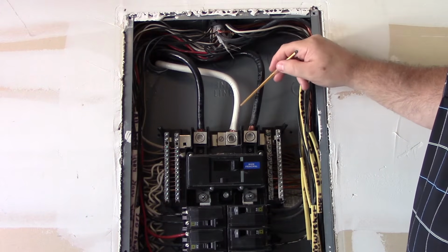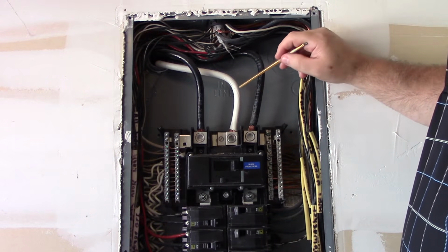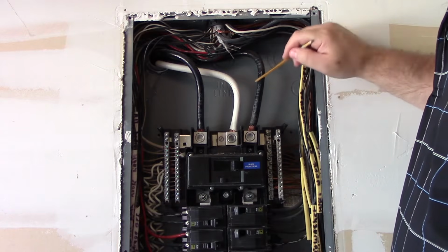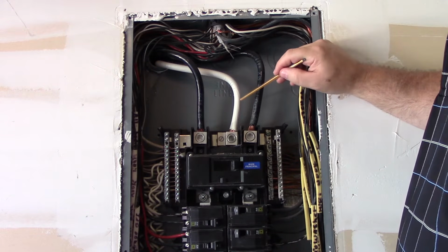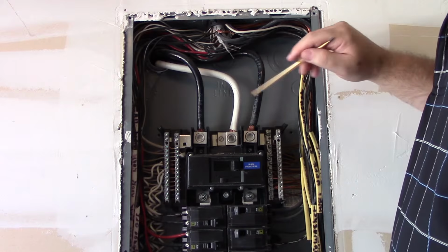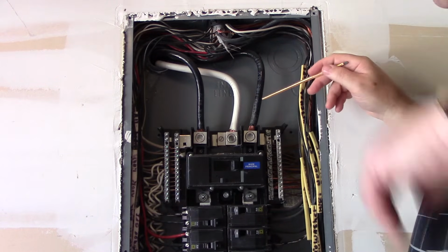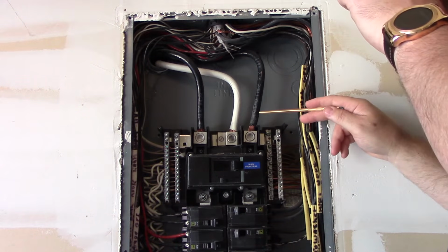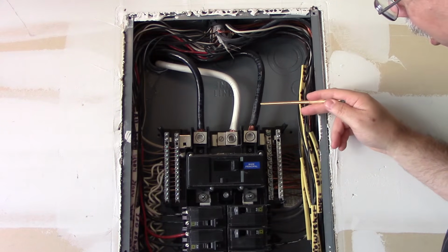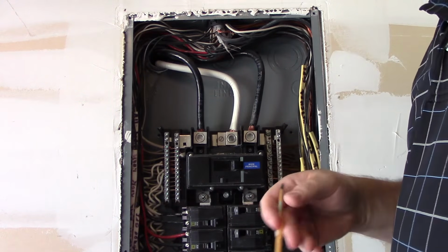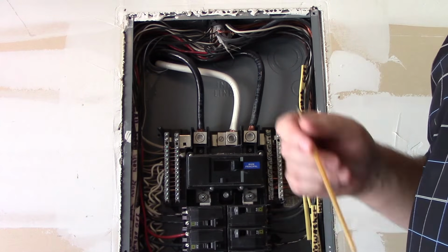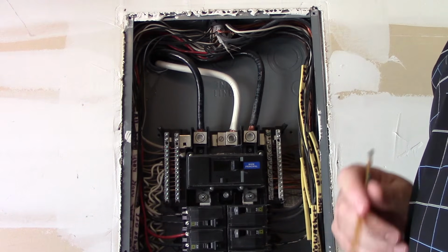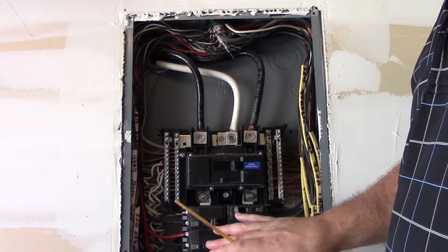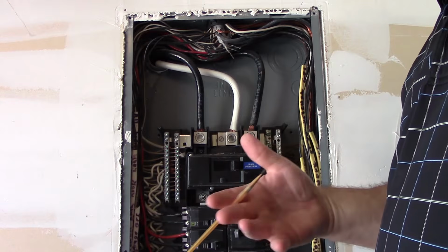Now, I happen to see right here, and you won't always get this lucky, on this grounded conductor, which is the same size here, it says 2/0 AWG. So I happen to know that these are also 2/0 because you can actually see the writing right here on the side. It says 2/0 right here. And I know that in accordance with 310.15(B)(7) of the National Electrical Code, if this panel handles 100% of the load, then I can use that reduced ampacity table for the sizing of these conductors.